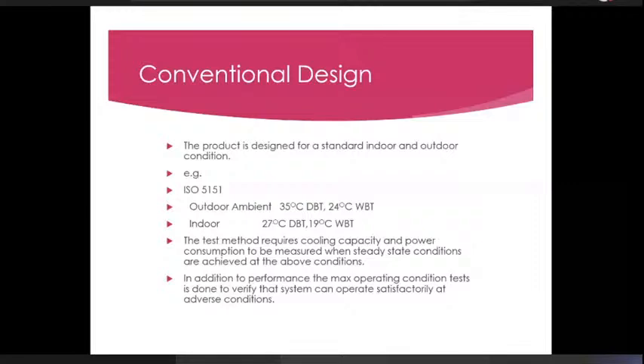Now this test requires cooling capacity and power consumption to be measured when steady state conditions are achieved. So we need to run the air conditioner such that for a period of 1 hour, for readings taken at intervals of 10 minutes, the change in these conditions does not exceed a certain number that is defined in the standard. I think it's either 0.2 or so. So once we get that level of stability, then we calculate the cooling capacity of the unit, and that becomes our indicator of rating the unit.